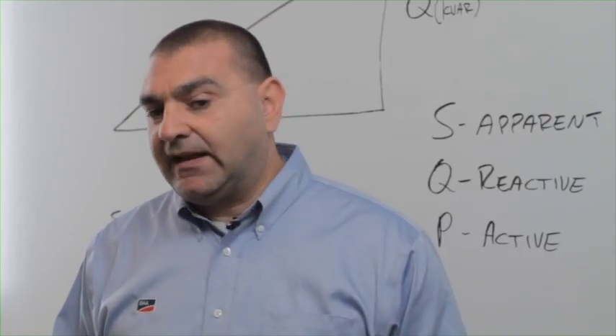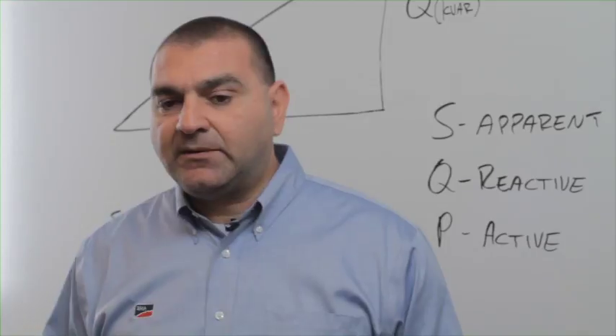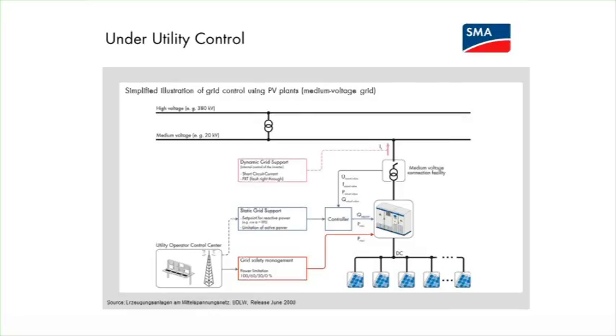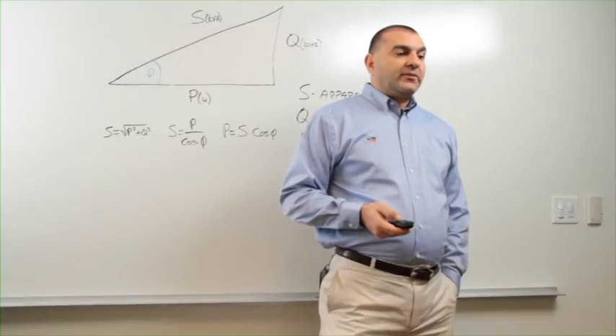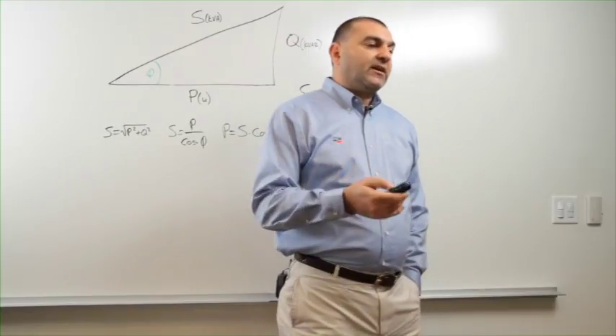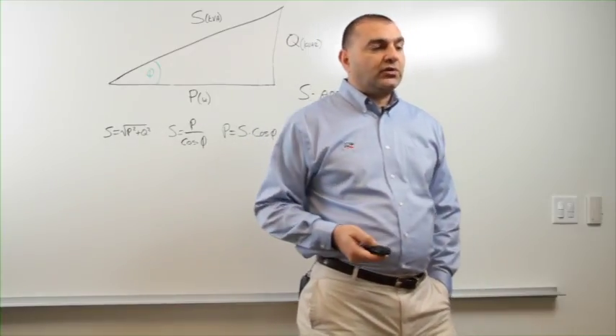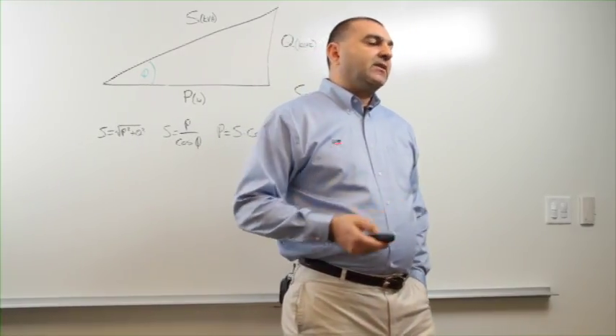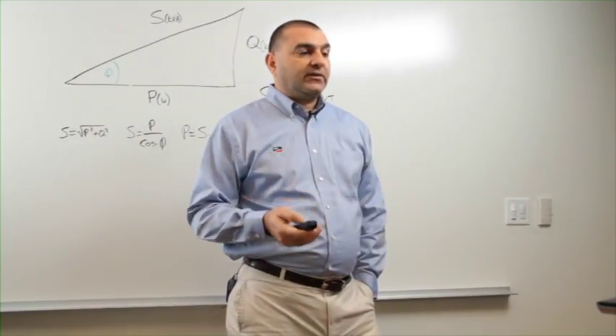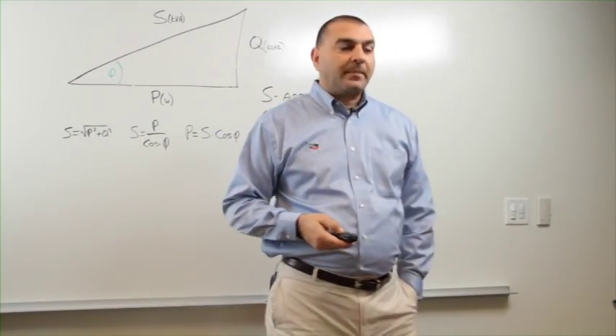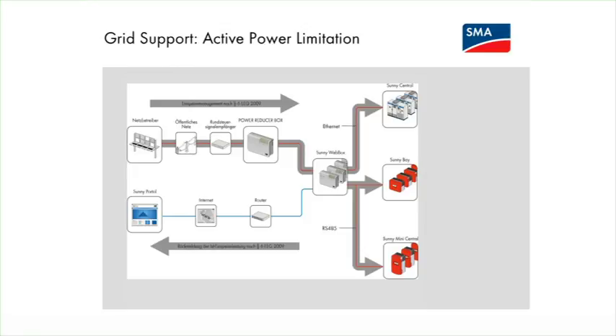The beauty of this is that all that I just talked about is under utility control, and that's what utilities like. They like to be able to control these plants and dispatch those units, whether you're dispatching megawatts, dispatching megavars, or setting the voltage requirements on the grid. SMA also is equipped with the appropriate controllers to facilitate this task in integrating it not only to the grid, but to the utility control center. Let's talk about the active power limitation.